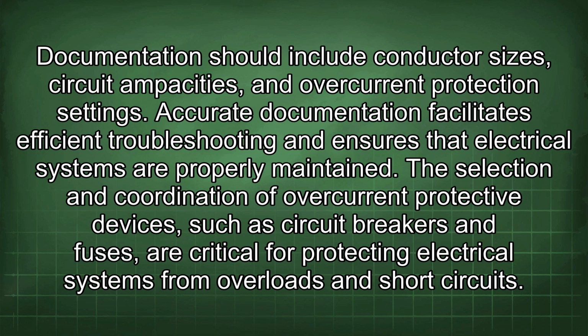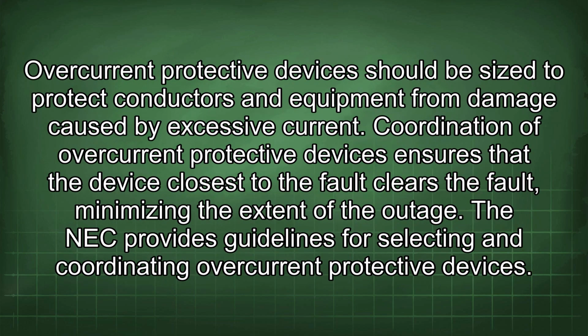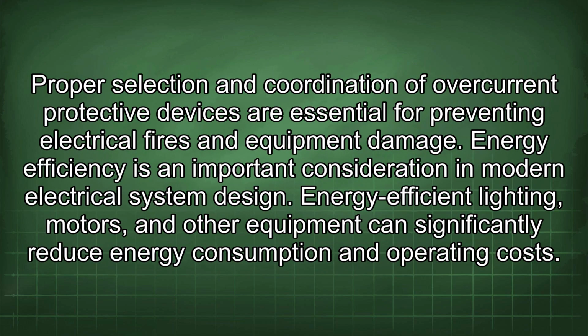The selection and coordination of overcurrent protective devices, such as circuit breakers and fuses, are critical for protecting electrical systems from overloads and short circuits. Overcurrent protective devices should be sized to protect conductors and equipment from damage caused by excessive current. Coordination of overcurrent protective devices ensures that the device closest to the fault clears the fault, minimizing the extent of the outage. The NEC provides guidelines for selecting and coordinating overcurrent protective devices. Proper selection and coordination of overcurrent protective devices are essential for preventing electrical fires and equipment damage.